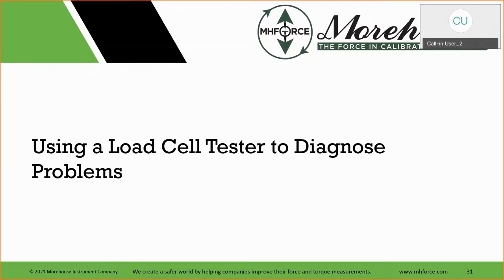Is it worth buying a load cell tester to monitor and check my performance? What about my calibration provider? If I send it out, before it goes out for cal, I take all my zero balances, and then it comes back and they're higher. You think the calibration provider overloaded it? We have those. Unfortunately, we overloaded a load cell this year. We always tell the customer it's one of the worst calls you can possibly make, because you lost history, unless you grabbed the history and did it on the last run. But yeah, somebody does. We have protocols and such in place, but often if you're training new technicians, which we were doing, a new technician within their first 3 months, there's a high probability that they're going to do something wrong. They're going to be trying to pay attention to something else, and they're going to magically overload the load cell.